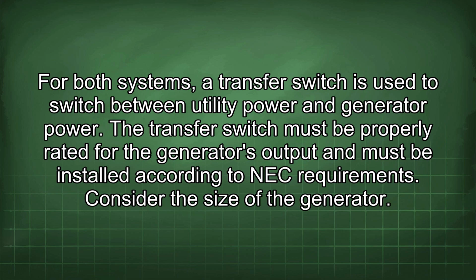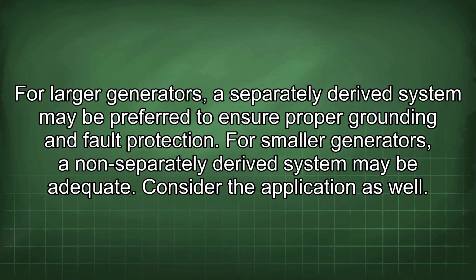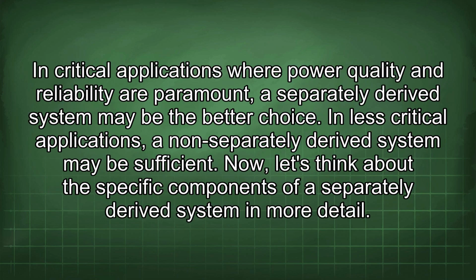Consider the size of the generator. For larger generators, a separately derived system may be preferred to ensure proper grounding and fault protection. For smaller generators, a non-separately derived system may be adequate. Consider the application as well. In critical applications where power quality and reliability are paramount, a separately derived system may be the better choice. In less critical applications, a non-separately derived system may be sufficient.